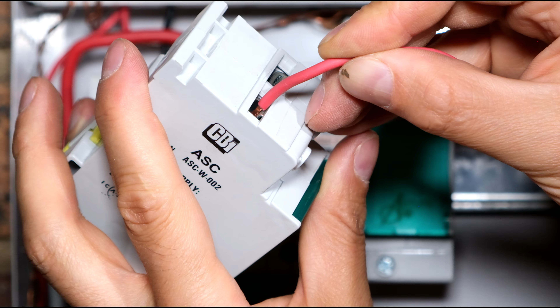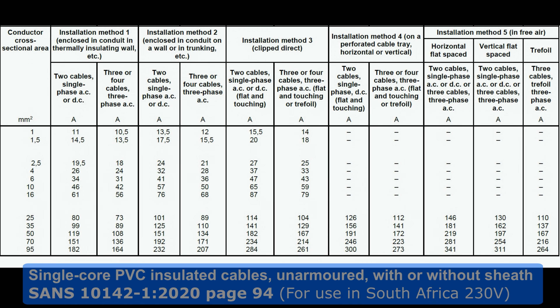The circuit breaker is 10 amps, so I'm fine with using a 1.5 millimeter wire. If you have a 20 amp circuit breaker here, you will need to use a thicker wire. I will quickly show you a guide for the wire size thickness. Now the timer needs to feed the load. The load is going to come out there.